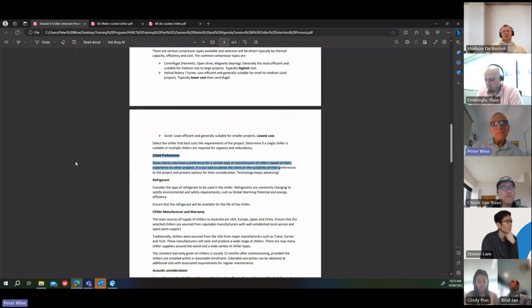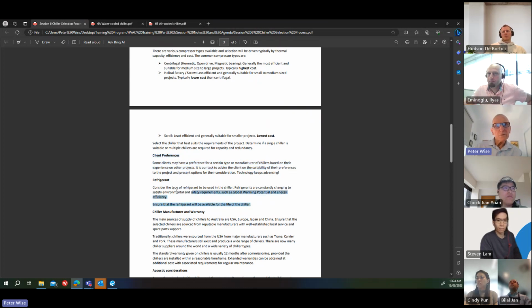Client preferences. Some clients have multiple properties, and they might have a preference for a certain type or manufacturer of chiller based on their experience in other projects. And this happens. They have their favourite chiller. It's our task to advise the client on the suitability of their preferences to the project and present options for their consideration. The technology keeps changing, so they might be used to an old style chiller that has been very reliable, but efficiencies have increased, types of chillers have changed, compressors have changed, so there are lots of options available, and we need to find the best option for the project. Obviously, cost is an important factor, but efficiency is very important as well.